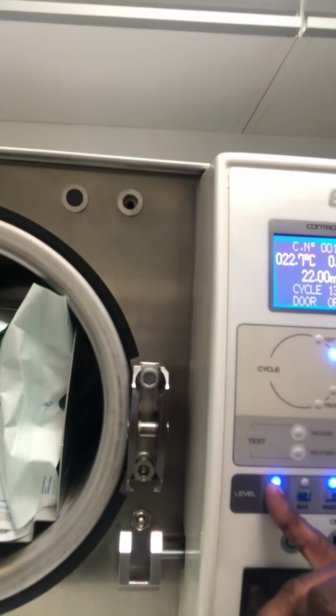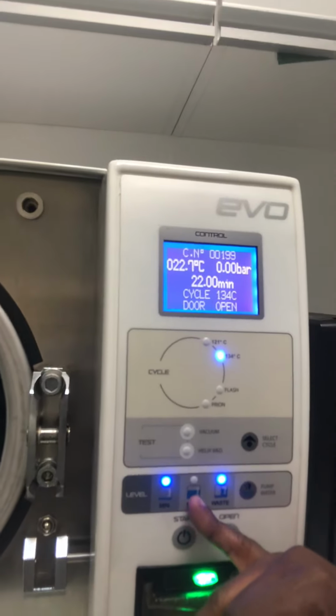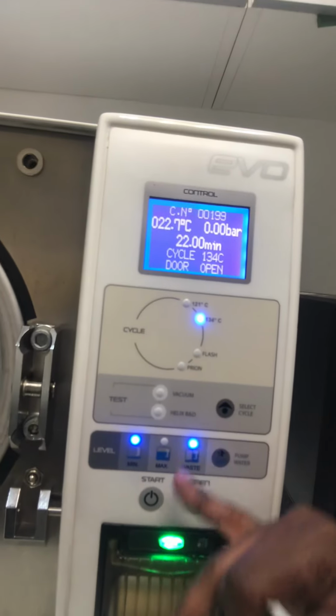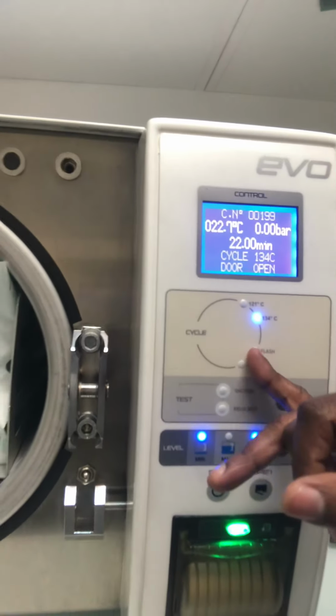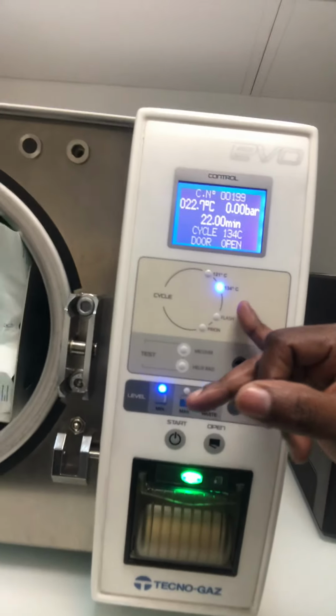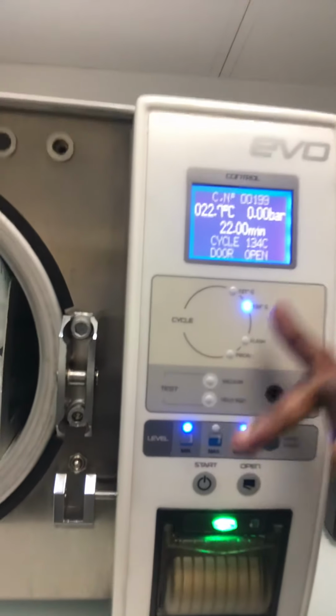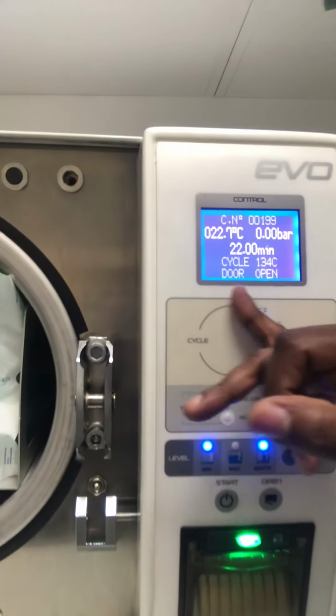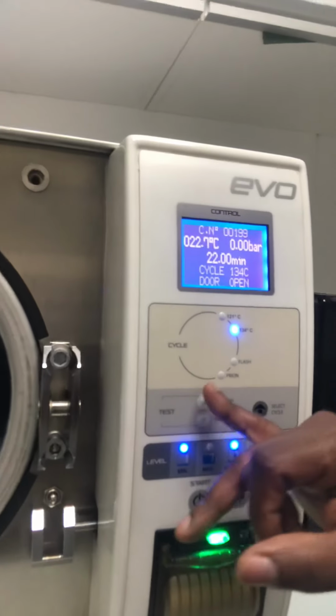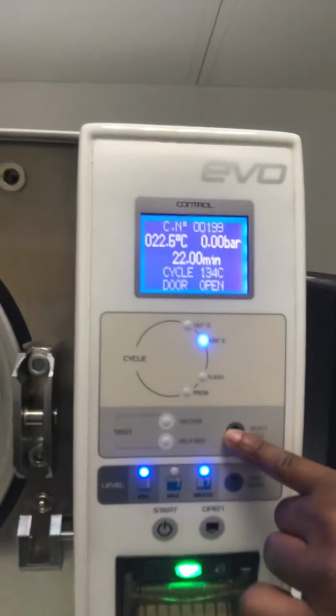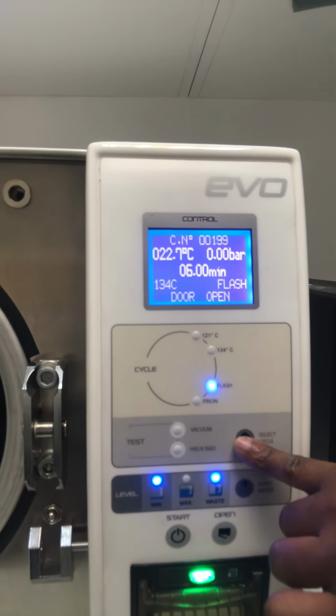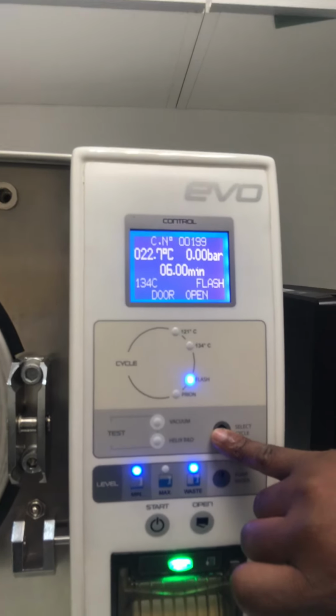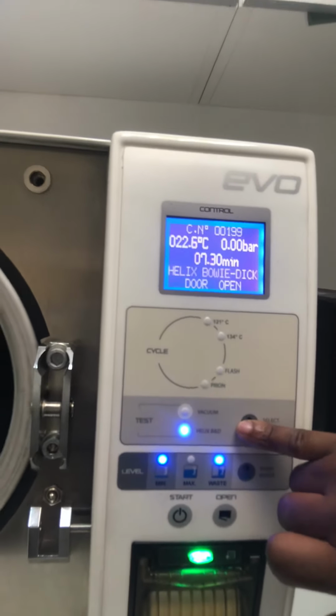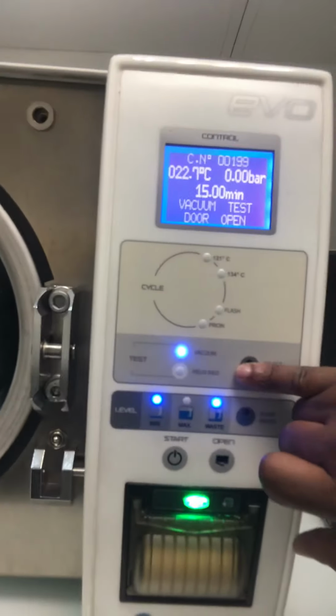Once this blue light goes off, then all the lights, so if I remove waste, the light will go off. If the water is enough to do the sterilization, then the blue light will go off. Then we have the cycle. We have 121 degrees Celsius, 134. Ours is 134. Then if I want to just flash, I'll put on flash or prion. So we have vacuum, where you select the cycle that you want. If I want flash, the sterilization machine will flash. If I want prion, same. If I want vacuum, same, just like that.